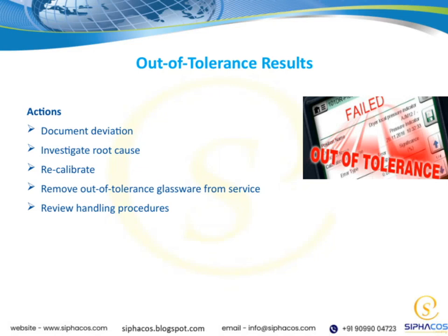Let's talk about what to do when we encounter out-of-tolerance results. First, it's crucial to document the deviation thoroughly. This helps us keep track of what happened and provides a record for future analysis. Next, we need to investigate the root cause of the issue. Understanding why the deviation occurred is key to preventing it from happening again. Recalibrating the equipment might be necessary to ensure accuracy moving forward. If we identify any glassware that is out of tolerance, we should remove it from service immediately to avoid contaminating other samples or experiments. Lastly, reviewing handling procedures is important. This ensures everyone is following best practices and helps us improve our processes overall. By taking these actions, we maintain the integrity of our results and uphold the quality standards we're committed to.